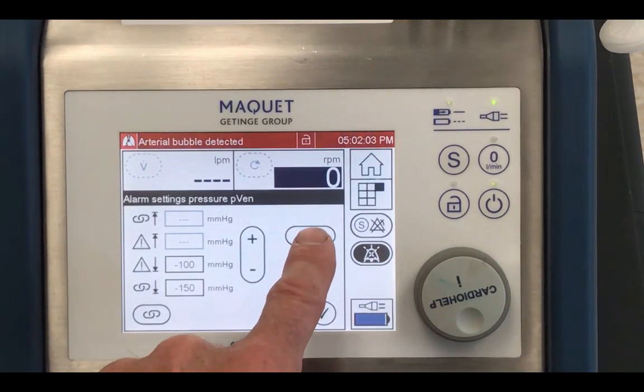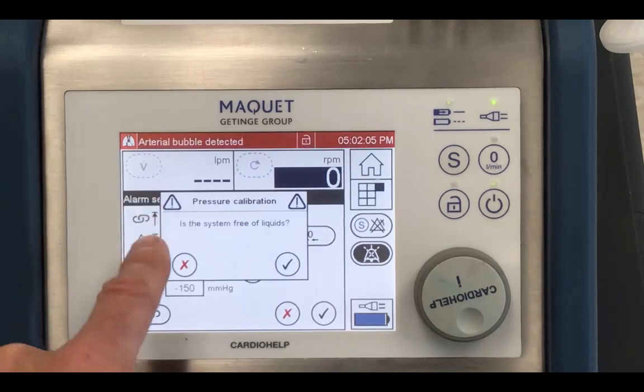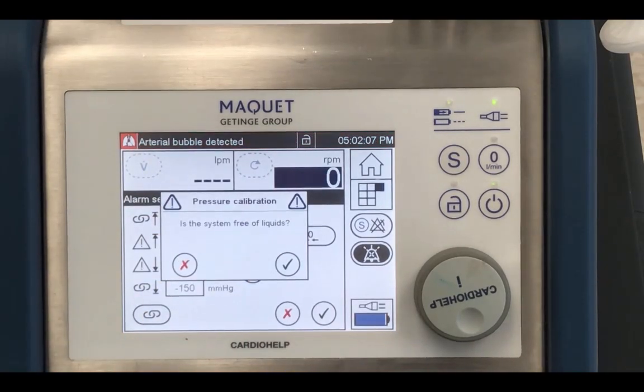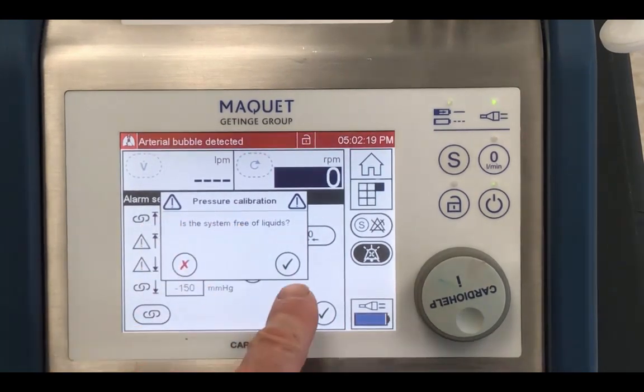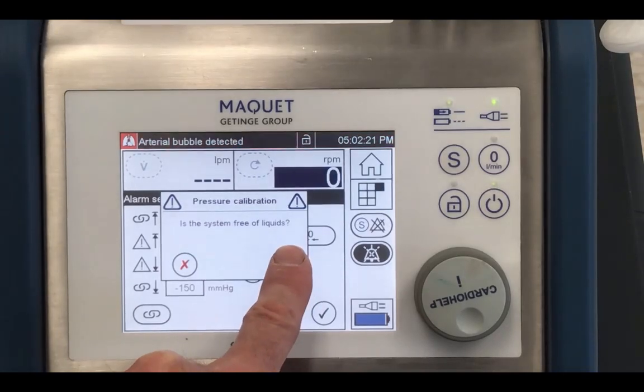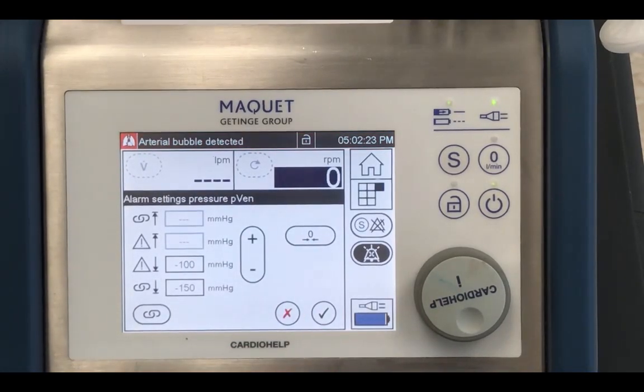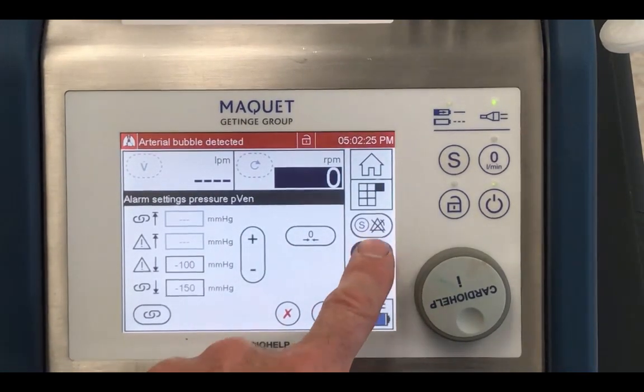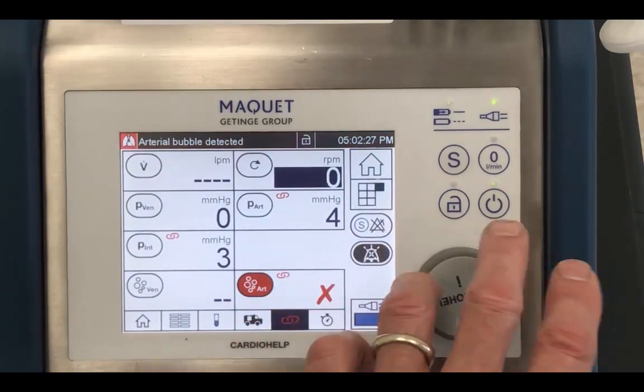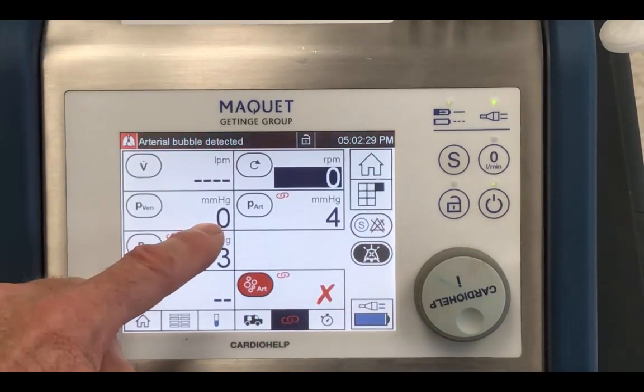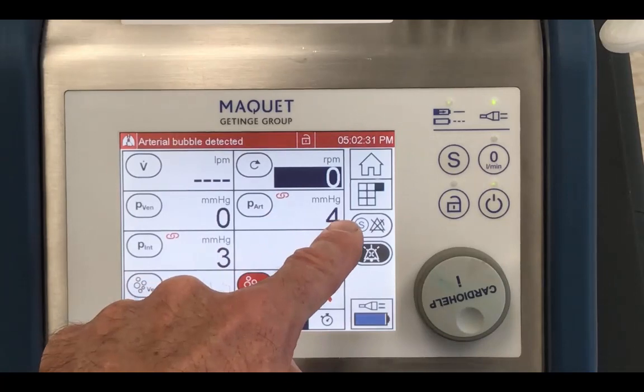If we select that button, it's going to say, is the system free of fluids? And you have to say yes. They want you to zero the transducers when they're all under atmospheric pressure, so they all have the same reference point. So we're going to say it is free of fluid. My circuit doesn't even have tubing on it over there, and I hit that. And now when we come back and look at this screen, we should see that the venous line pressure equals 0. The P arterial is equal 4.